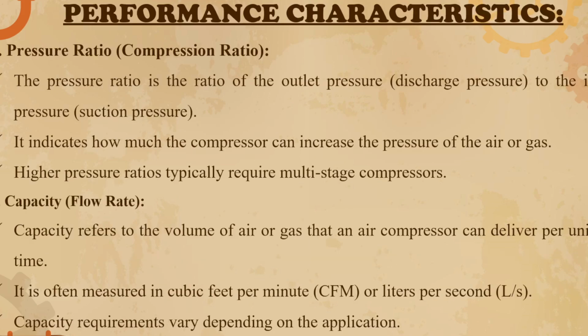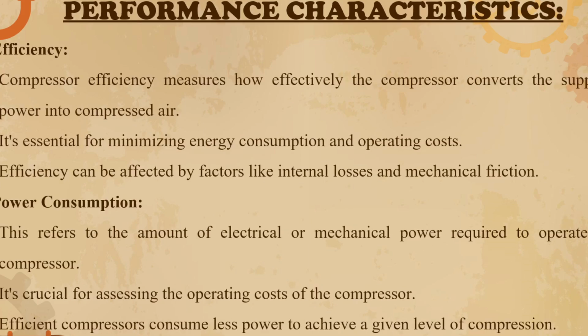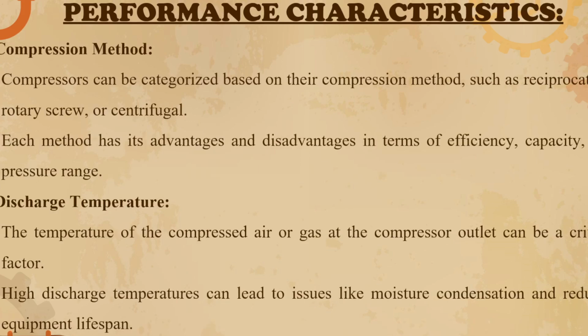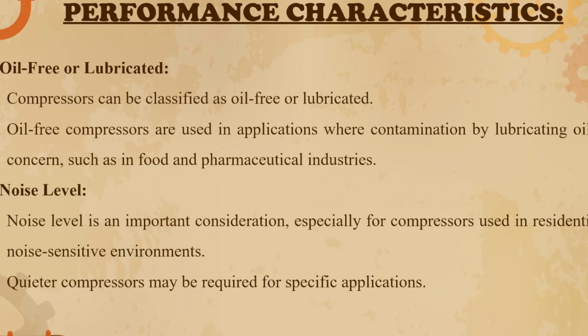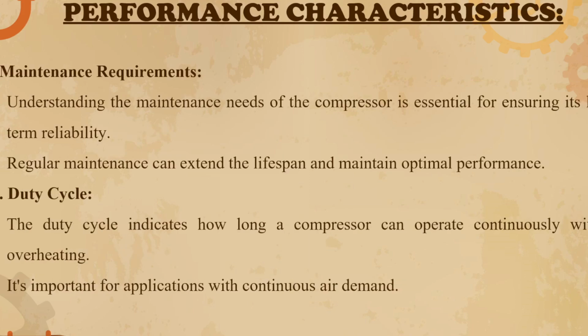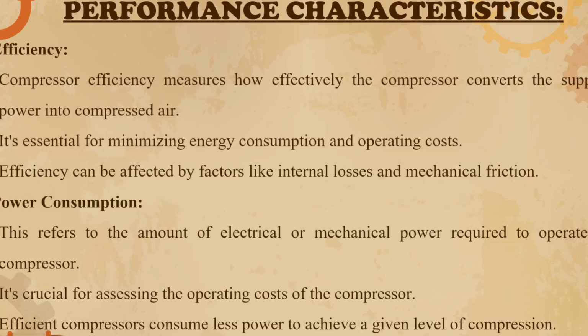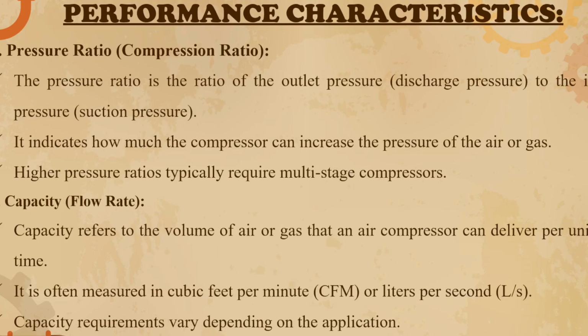For the performance characteristics of the air compressor, it includes pressure ratio, capacity, efficiency, power consumption, compression method, discharge temperature, oil-free or lubricated, noise level, maintenance requirements, and duty cycle. So, pressure ratio or compression ratio of the air compressor is the ratio of the outlet pressure to the inlet pressure. It indicates how much the compressor can increase the pressure of the air or gas, and higher pressure ratios typically require multi-stage compressors. Second characteristic is capacity or flow rate.